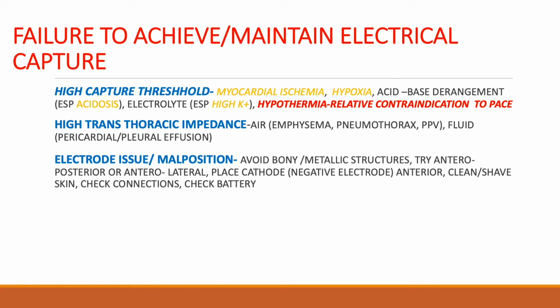There are some things you can do with electrodes. It does matter what your dipole is, where you're placing these pads. The ones we use are anterolateral because it's easier to do, but that doesn't always work well. So if that doesn't work, try an anteroposterior placement. Make sure the surface contact between the pads and the patient is good and clean. That may mean you have to shave the patient, or certainly get sweat and blood off of them and dry it off, because if you don't have good contact between the electrodes and the skin, that may be a problem. Obviously, you want to check your batteries and check the connections to make sure they're all okay.